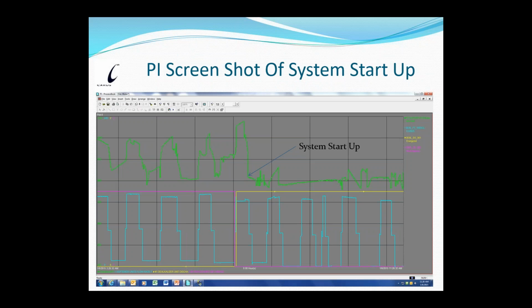So is there a difference in the scaling? Because I see at the bottom, when the softener does run, it is still running at full, whatever the previous GPM is. But if you were to look at the jumps in the green line, they're not corresponding. Well, they are, because like I said, it's scaled differently. What I do when I build my PI troubleshooting screens is build them so I can see what the process is doing. So the PI screen gives me the ability to have multiple scales for every data point that I'm looking at.